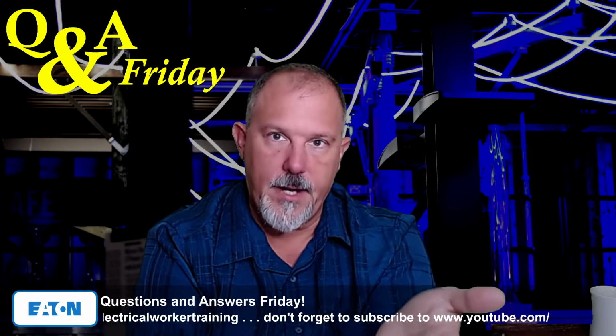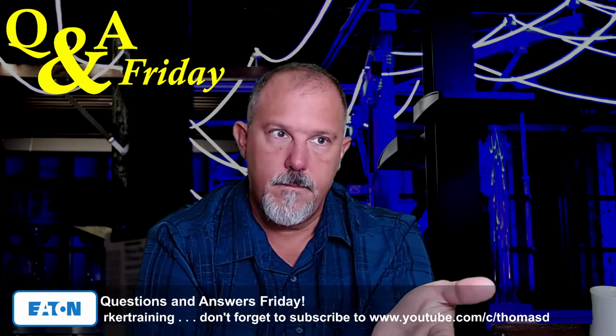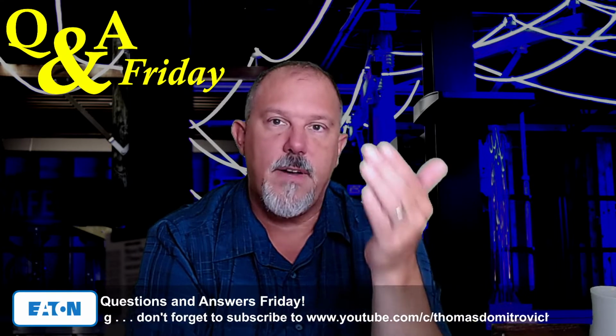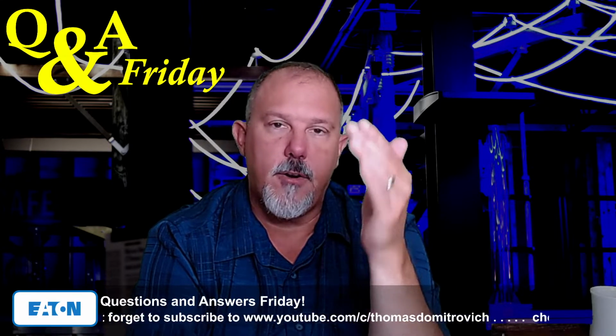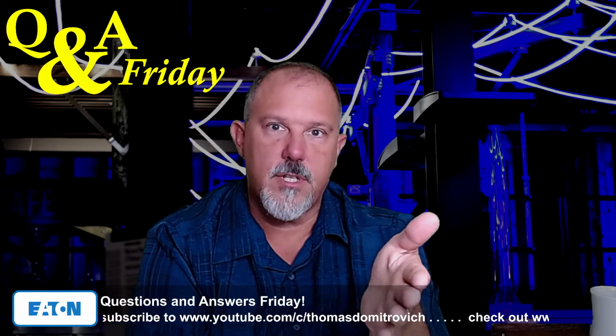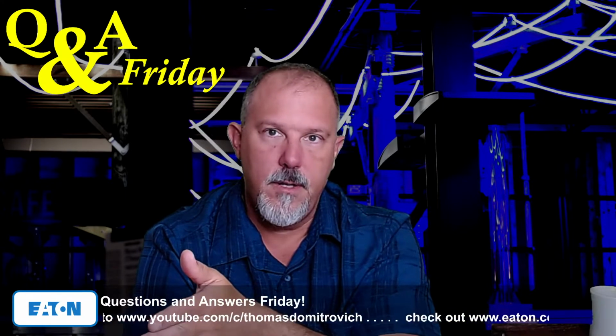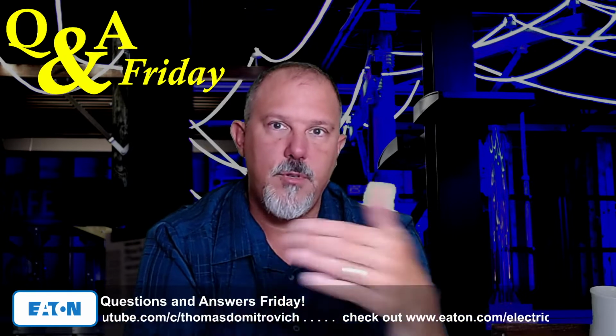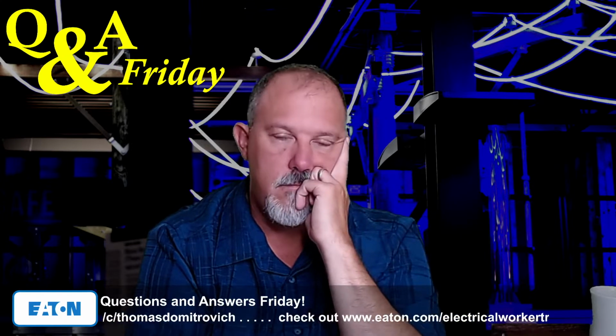That's 100% rated. If I used 100 amps worth of conductor, but I used a 125 amp breaker, I'd put a larger breaker in, and I'm using the conductor at its ampacity.